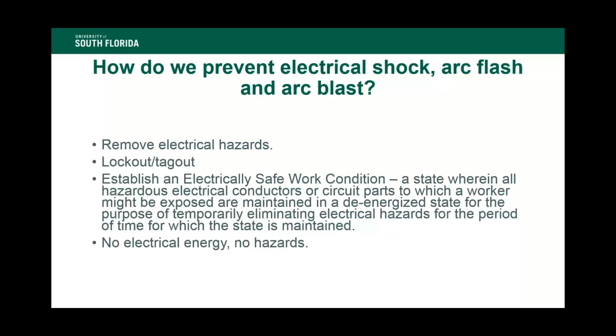It's a state wherein all hazardous electrical conductors or circuit parts to which our worker might be exposed are maintained in a de-energized state for the entire time that the worker is exposed to that equipment, okay? In other words, it's maintained as long as it is needed to be. So if we look at it from a practical standpoint, if we can remove the electrical energy, we have no electrical hazards, okay?